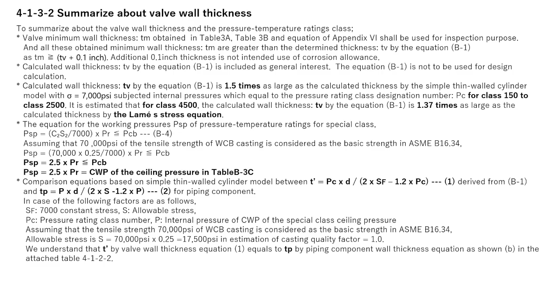Now we talk about the comparison of the wall thickness equations of the valve, pressure vessel, and pipe. Again, I assign the wall thickness equation for the valve as equation B1. The wall thickness equation for the pressure vessel in ASME Section 8 Division 1 is T equals P multiplied by D over 2 parenthesis sigma A multiplied by eta minus 0.6 multiplied by P in parenthesis, where P is the internal design pressure, D is the inside diameter, sigma A is the maximum allowable strength, and eta is the welding joint efficiency.